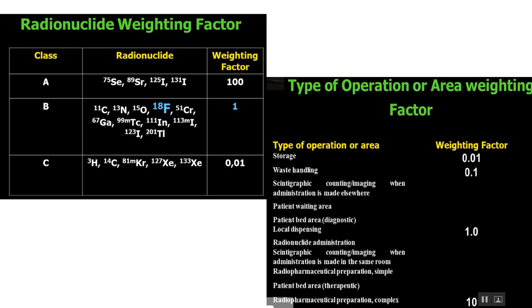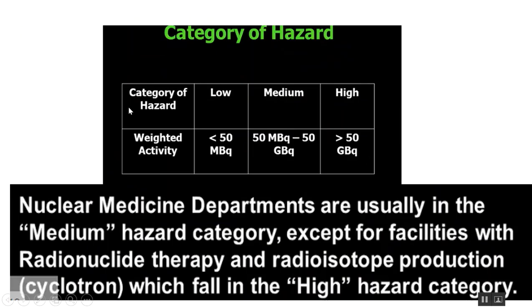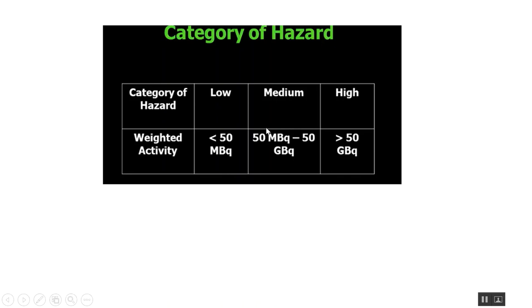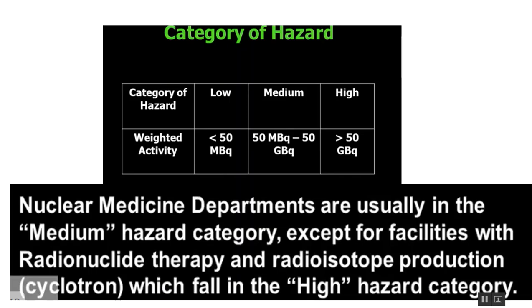The hazard categories are: low hazard — weighted activity less than 50 MBq; medium hazard — 50 MBq to 50 GBq; high hazard — greater than 50 GBq. Most nuclear medicine departments fall in the medium hazard category, except facilities with radionuclide therapy and radiopharmaceutical production like cyclotrons, which fall in the high hazard category.